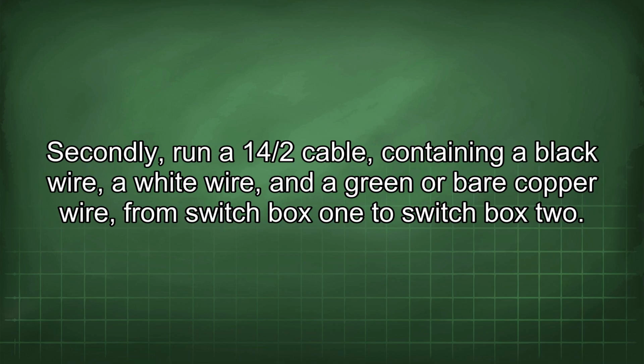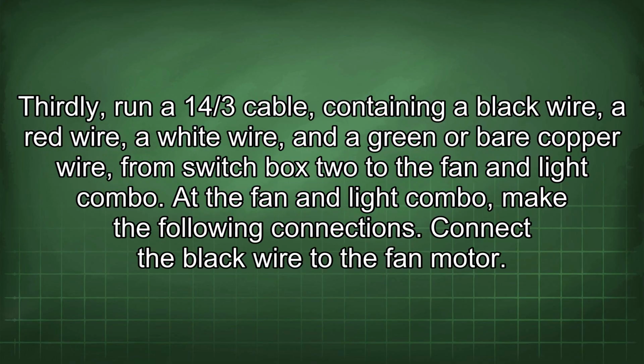Secondly, run a 14/2 cable containing a black wire, a white wire, and a green or bare copper wire from switch box 1 to switch box 2. Thirdly, run a 14/3 cable containing a black wire, a red wire, a white wire, and a green or bare copper wire from switch box 2 to the fan and light combo.